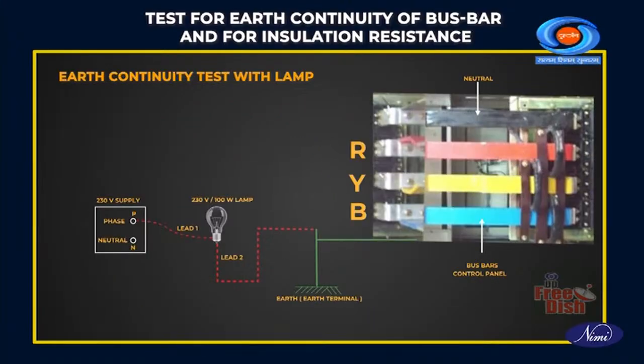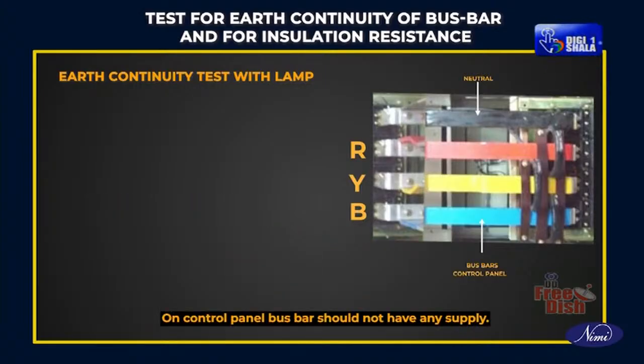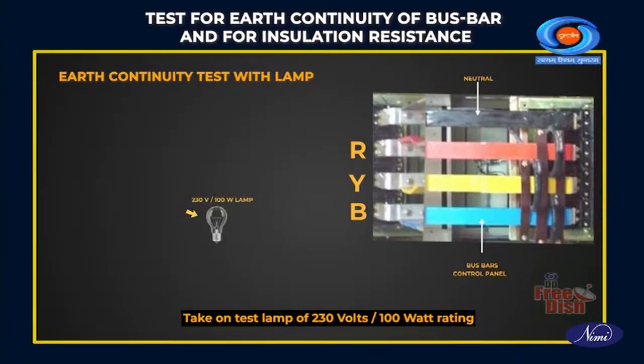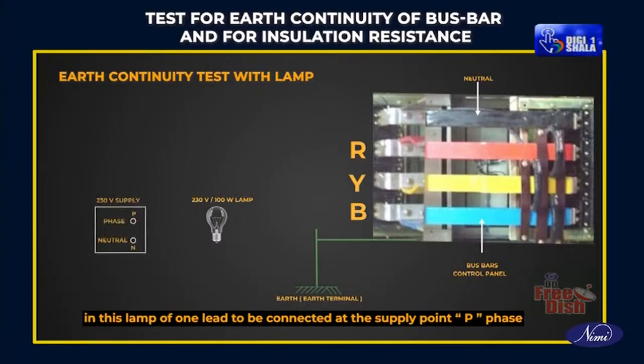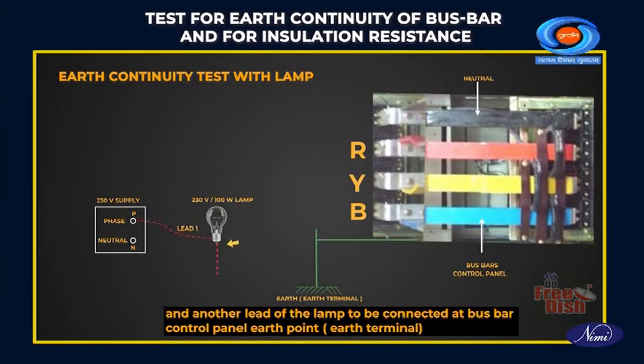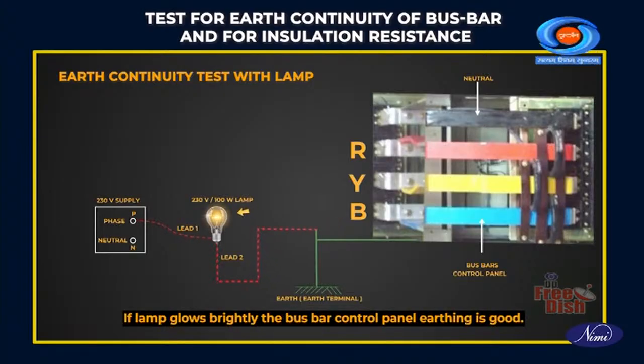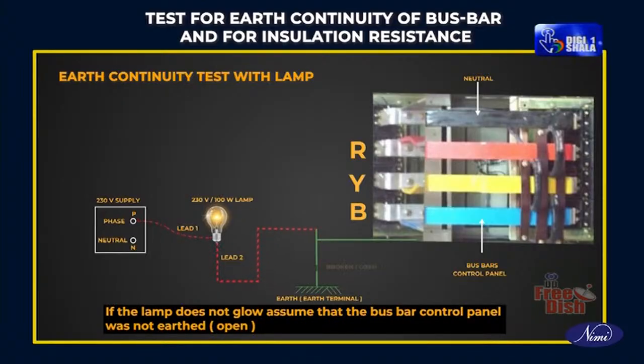Earth continuity test with lamp. On the control panel, the bus bar should not have any supply. Take one test lamp of 230 volts, 100 watt rating. One lead is to be connected at the supply point, the phase, and the other lead of the lamp to be connected at the bus bar control panel earth point, that is the earth terminal. If the lamp glows brightly, the bus bar control panel earth is good. If the lamp does not glow, assume that the bus bar control panel was not earthed, which means open.